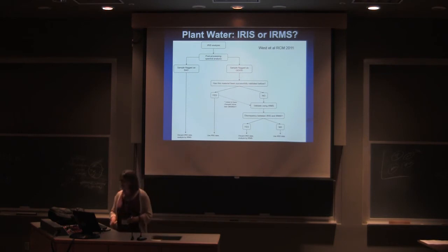But they still have not fixed it, so I caution you, if you're going to do it, to do some subset of your samples that you run on an IRMS to make sure that those values compare and you can demonstrate it. Otherwise, you probably are going to end up with problems in going through review. I certainly don't let papers through that have leaf water measured on a laser system.